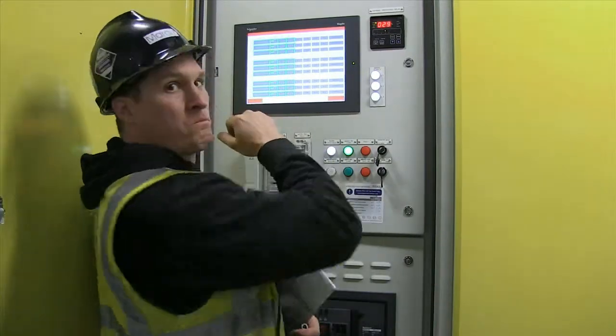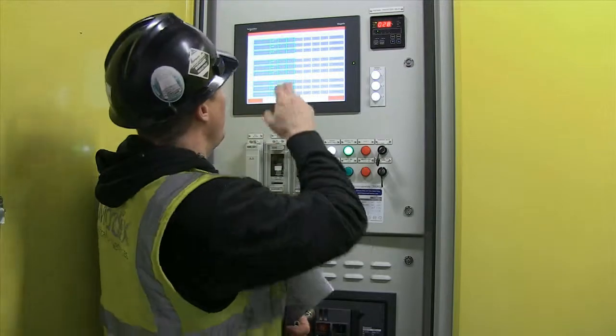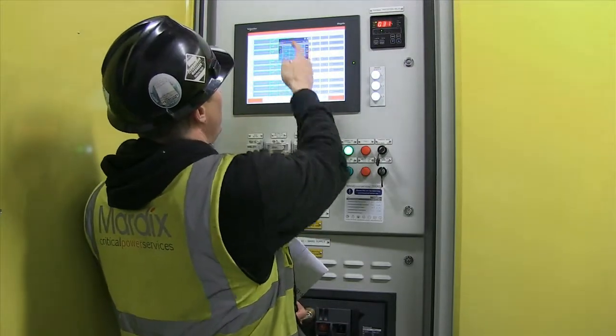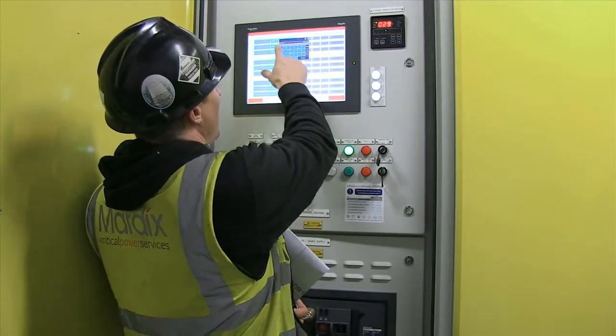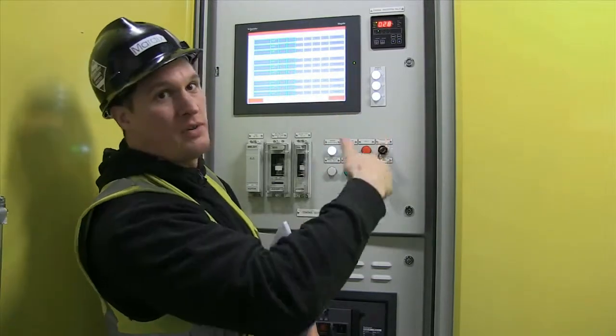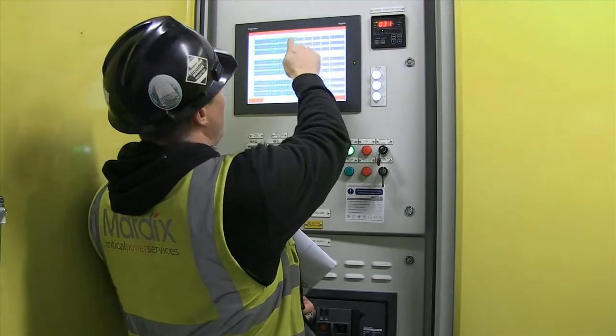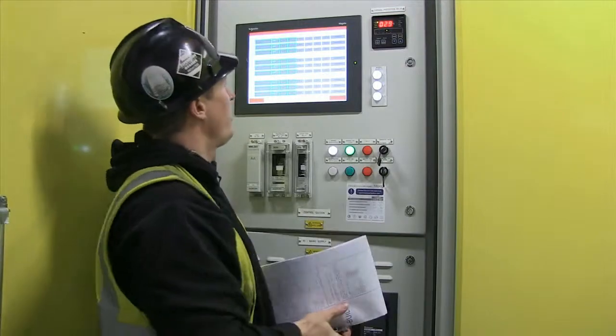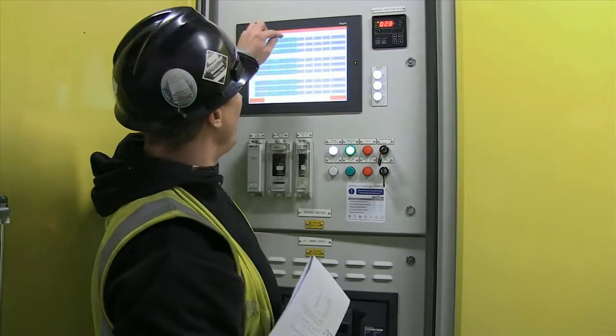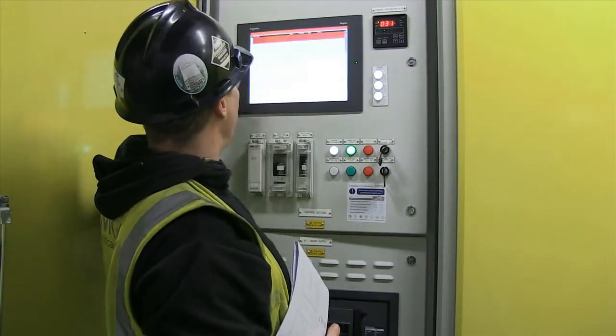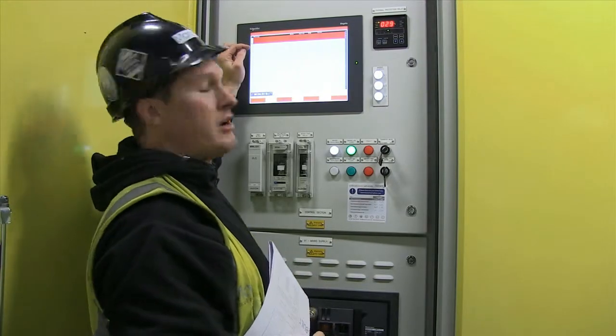And then buttons go red, don't they? Yeah, that's it. When it goes overload, because you've got minimum, maximum. If I go to minimum, I set the minimum to zero. I won't change it because it'll go into alarm, and then you have to put load on it to clear it. But if you go on to maximum of 32, so if someone's drawing more than 32 amps, like you said, that will go red, that will flash. And that will just pop up in there as an overcurrent alarm.